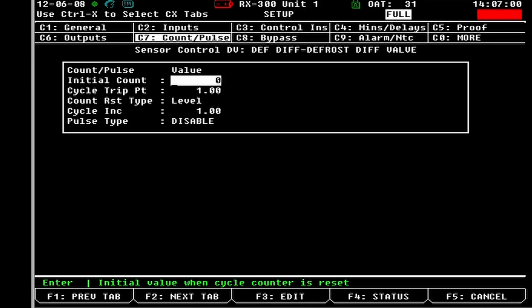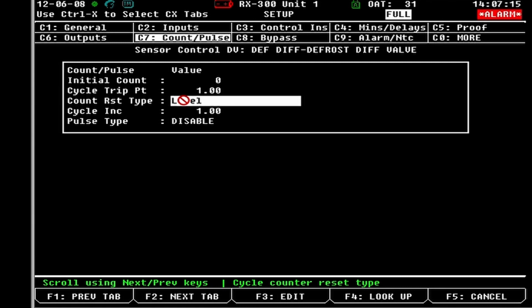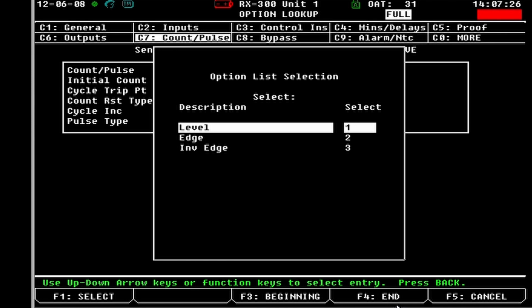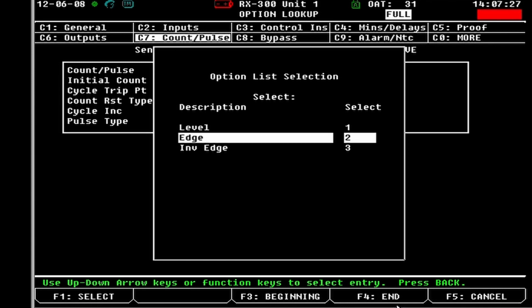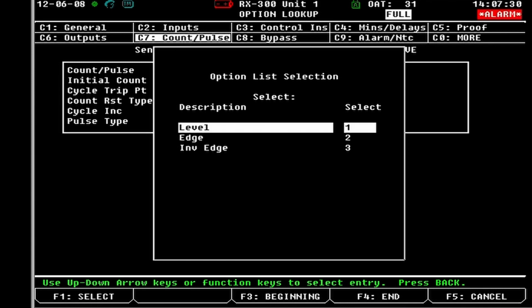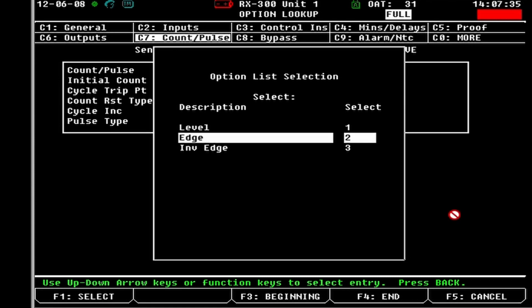So on the count and pulse, you have the initial count. And then cycle trip point. So a 1 is how many times it has to cycle before it trips. Counter type reset is level. So level means anytime it goes from on to off or off to on, it's going to count. So if you hit here, look up, and then edge. Level is a change of state, and then edge is when it cycles from on to off, and then Inv Edge is off to on.